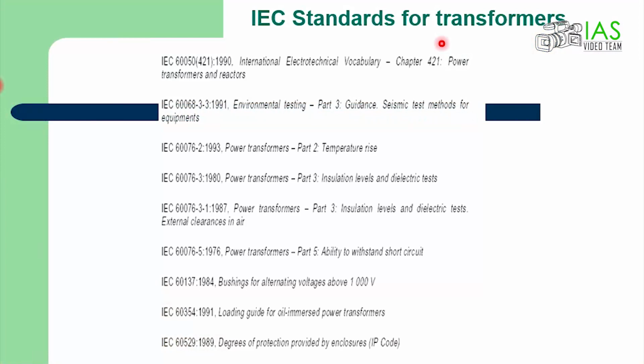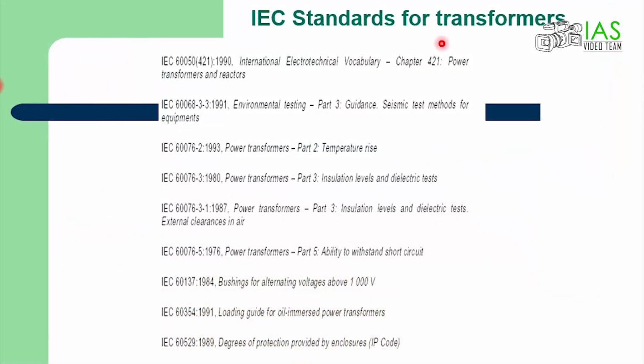So, some IEC standards here. I think you are getting the soft copy of this, and you can refer to the IEC standards relevant for each section. Now if you take the first one, electrotechnical vocabulary, this terminology is coming from IEC 50, and for transformers the relevant chapter is 421 of IEC 60050, right? And we take power transformers IEC 76-3, that is insulation levels and dielectric tests, right?